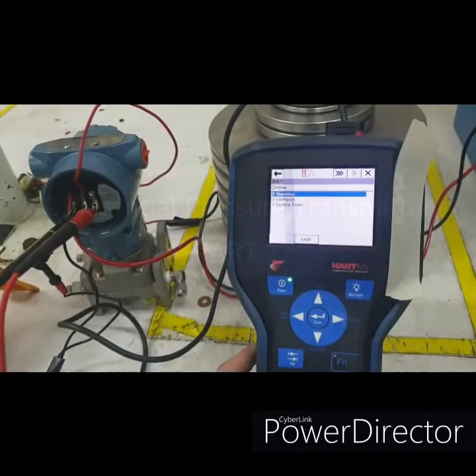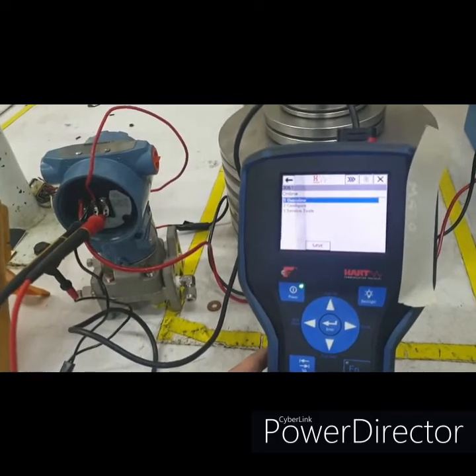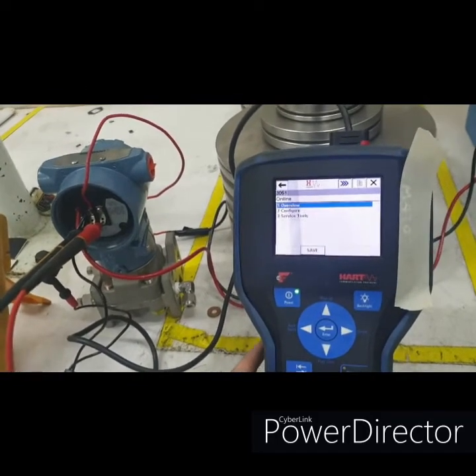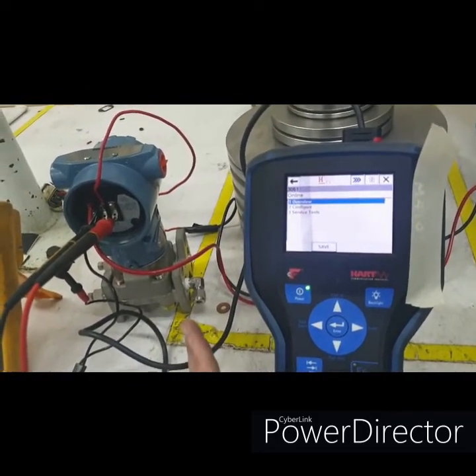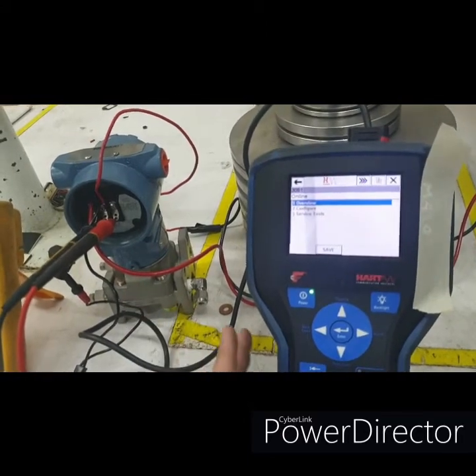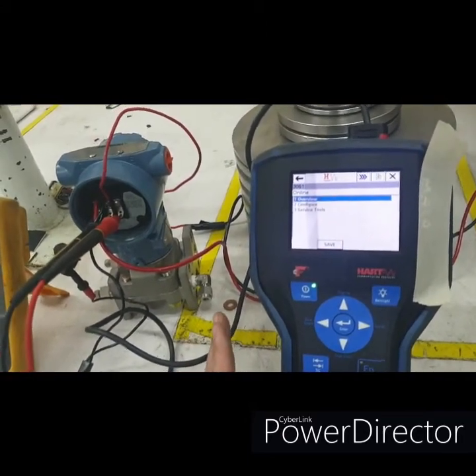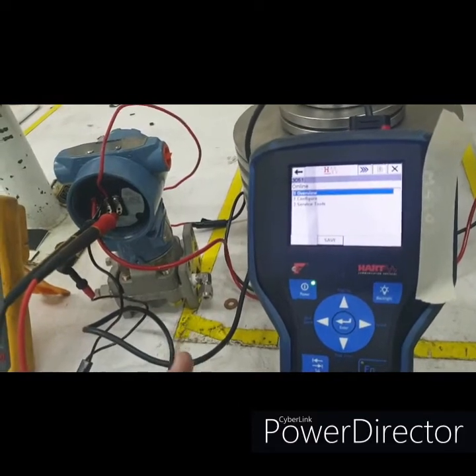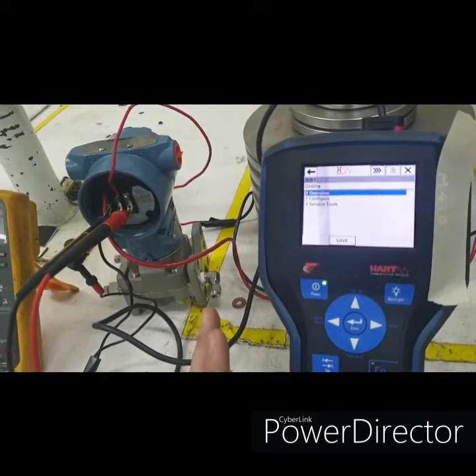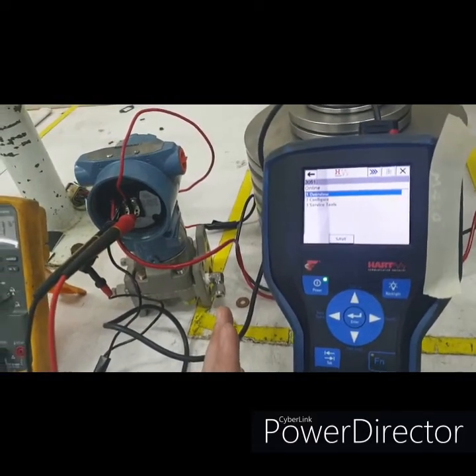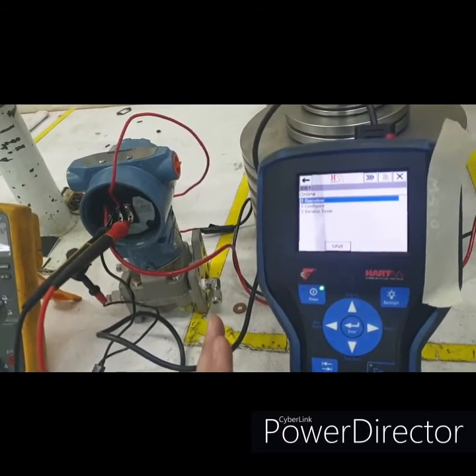Okay, so we will configure this transmitter according to our requirements. Let's say this transmitter we're gonna use in a filter that will monitor the differential pressure across the filter. So let's say the calibration range is 0 to 20 millibar.